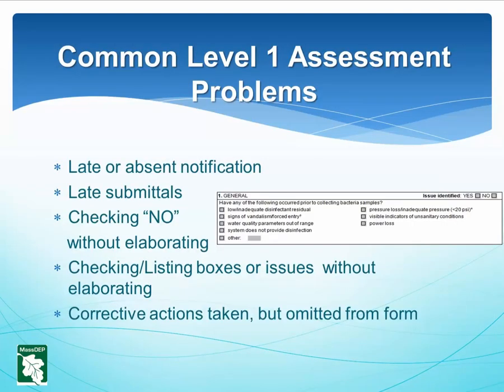Common Level 1 Assessment Problems: MassDEP has noticed failure to notify MassDEP of a trigger or late notification — in one region a submittal was 1.5 months late. Other problems include checking 'no' without elaborating, checking or listing a series of boxes or issues without elaborating, and few or no boxes checked without potential causes identified despite the system taking corrective action. Under the RTCR, MassDEP must be notified of an assessment trigger promptly. Elaborating when checking 'no' is important, and not identifying potential causes of contamination should mean taking a closer look at the system. Chlorination or flushing may not solve the problem. Assessors must fill out the Level 1 form as completely as possible to avoid issues down the line.